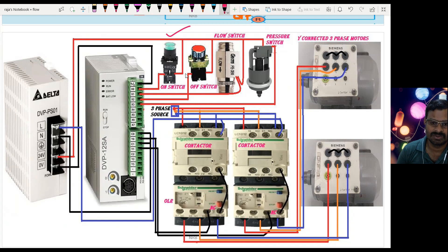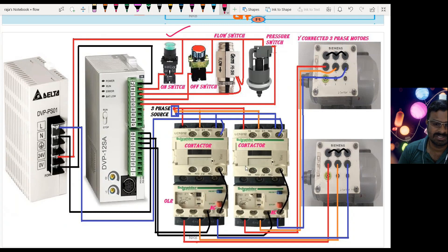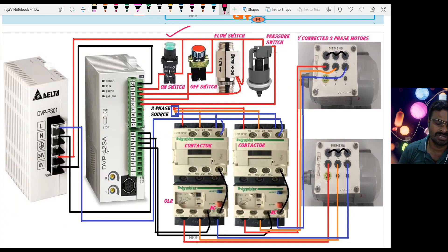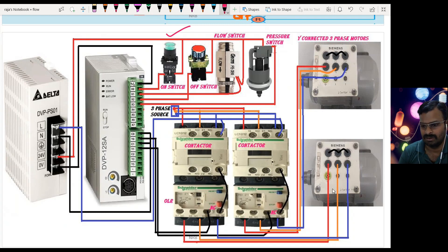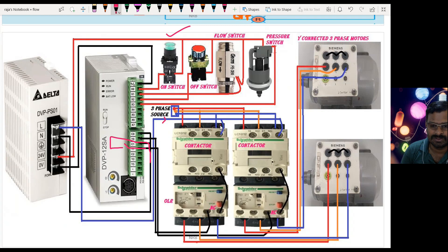The wiring is done so that the sensors act as sourcing devices and the input module acts as a sinking device. Similarly on the output side, the contactors act as sourcing devices and the output module acts as a sinking device. When the output coil is energized, the contactors get enabled and the motors turn on. The A1 terminal is the coil for the contactor, and there is an NC switch for the overload relay going back to the PLC output module.